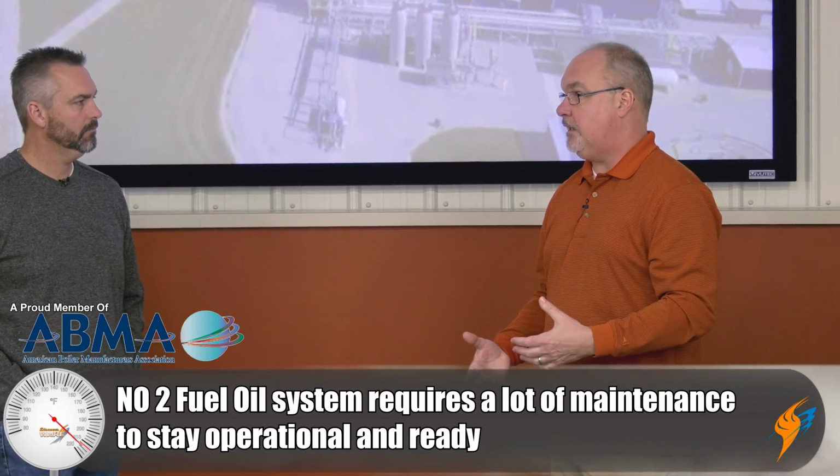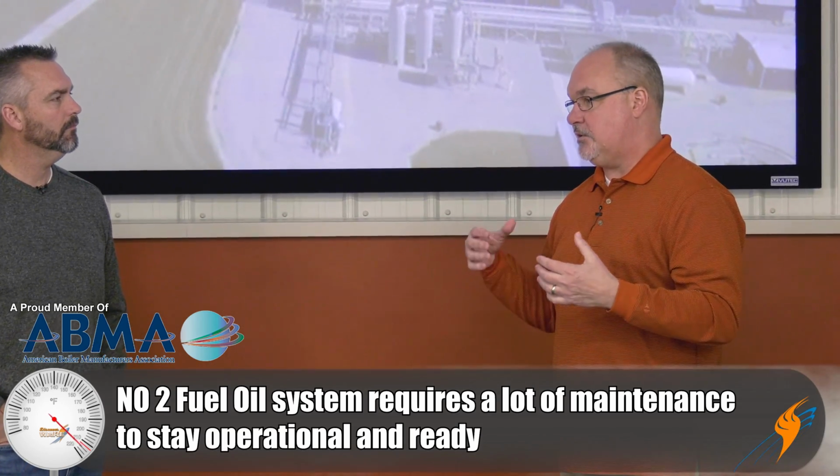Right. Why would you do an LNG over, let's say, a number two fuel oil as a backup? Well, in our experience, our number two fuel oil customers that have that as a backup, more often than not, are not doing the things they need to do to keep the system operating and ready. Your number two oils, if you're not circulating properly and testing periodically, you'll end up cracking it, it'll water out, and it won't work when you need it. So it's not that it can't be a good backup, but it takes a lot more attention. Where with an LNG or even a propane, they tend to just take care of themselves, and when you need it, it's there.